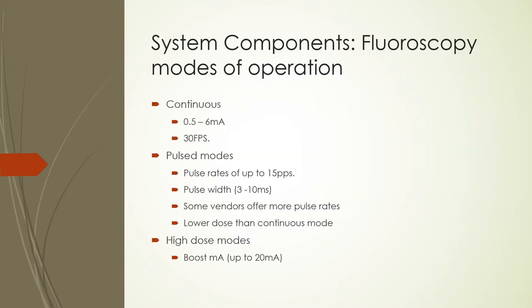Fluoroscopy can be acquired in a continuous mode or a pulsed mode. In continuous fluoroscopy, the machine produces a continuous x-ray beam of 0.5 to 6 milliamps tube current, and a video camera displays images at 30 frames per second — about 33 milliseconds per frame. For slow-moving objects, fewer pulses per second can be used; pulse widths range from 3 to 10 milliseconds. Pulse fluoroscopy offers better image quality for fast-moving objects at lower dose than continuous mode. High-dose or boost modes are available for thicker anatomies, boosting mA up to about 20 milliamps. In record or cine modes in CAT labs, some units can produce up to 600 milliamps.